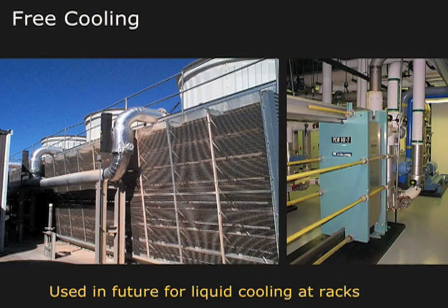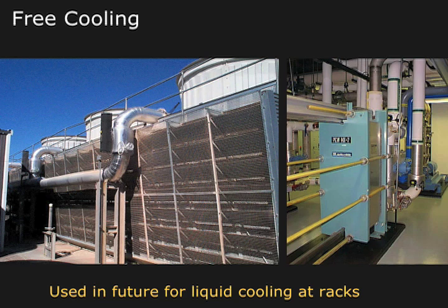And then we are going to set up the cooling towers in a way that they can work with the plate frame heat exchanger to do the water side economizer, water side free cooling, for the future liquid cooled racks that might come in.